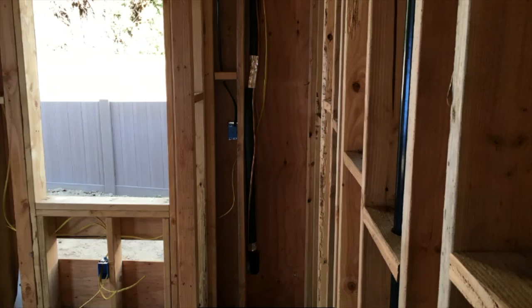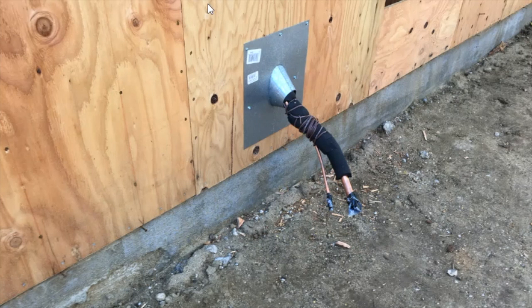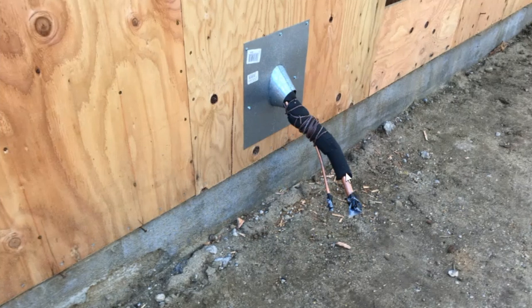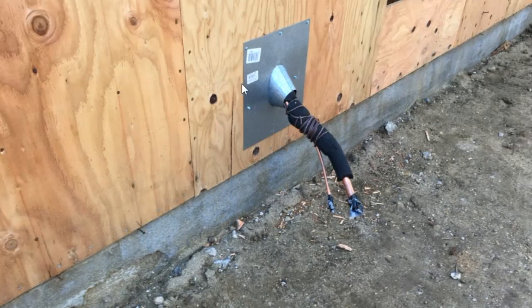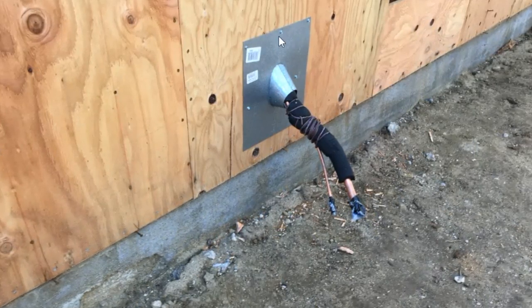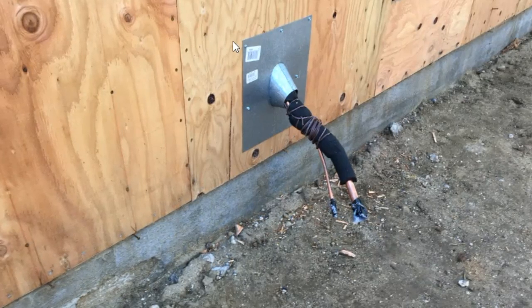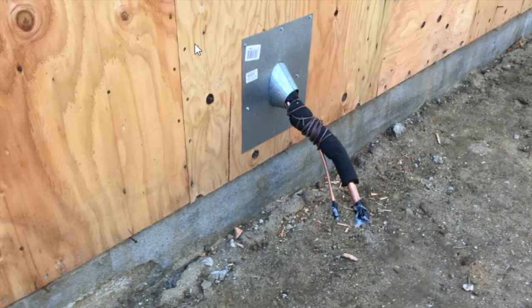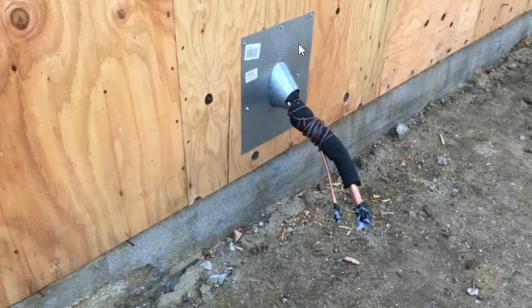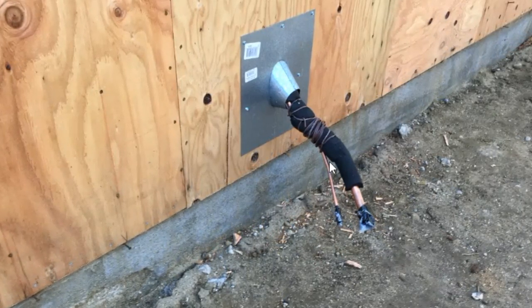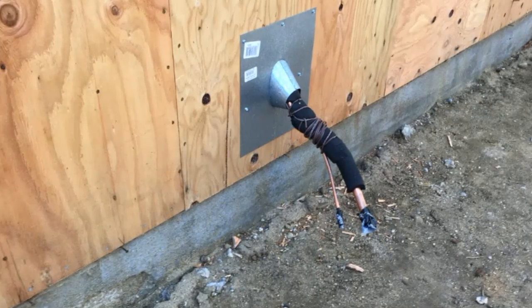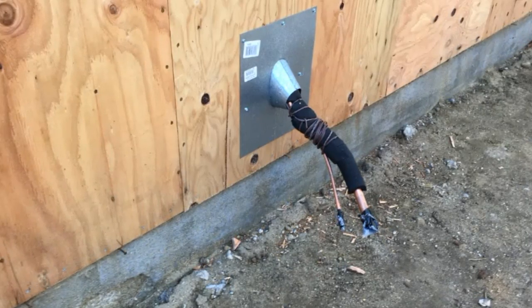We also ran during the rough-in process the refrigerant line, which comes down the outside wall and penetrates here for our location of our outdoor condensing unit. The lines are pushed out through the hole that we cut. We install a flashing around it, and then this will allow the people doing the outside work, the siding or stucco, to patch it. Once that is finished, then we will come back and set our equipment on a pad next to the line set.